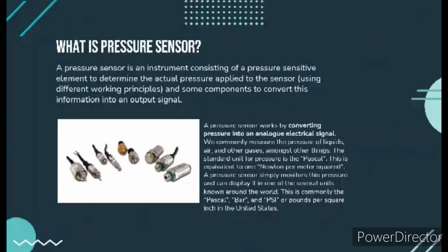What is a pressure sensor? A pressure sensor is an instrument consisting of a pressure sensitive element to determine the actual pressure applied to the sensor using different working principles and some components to convert this information into an output signal. A pressure sensor works by converting pressure into an analog electrical signal.